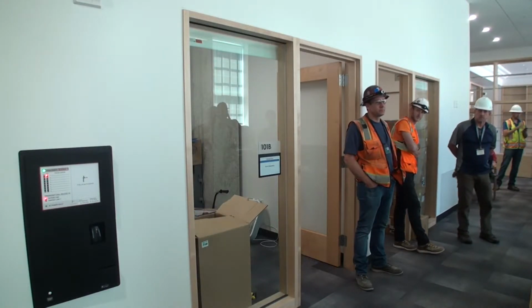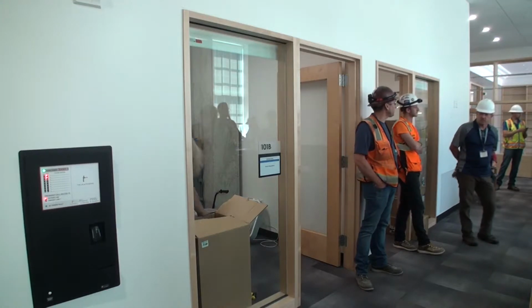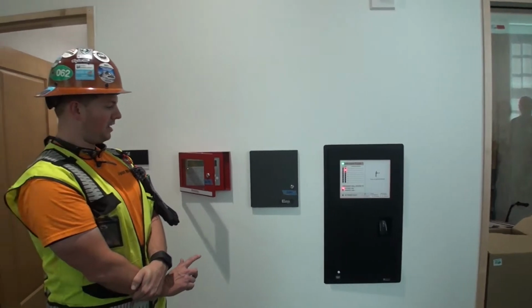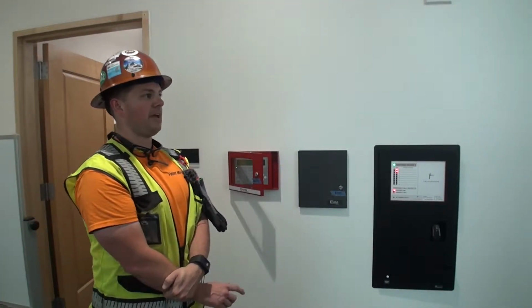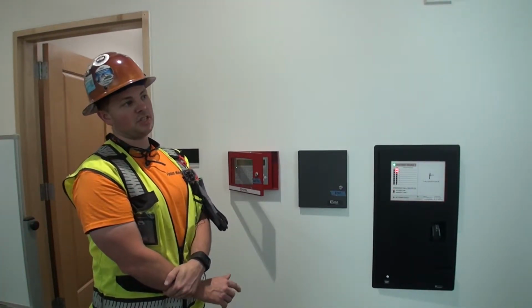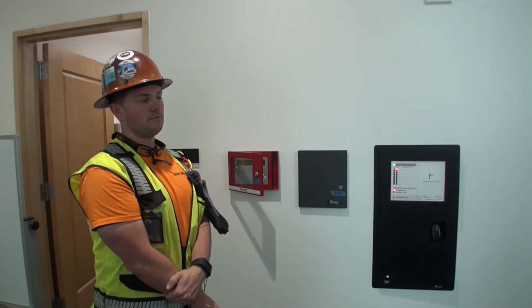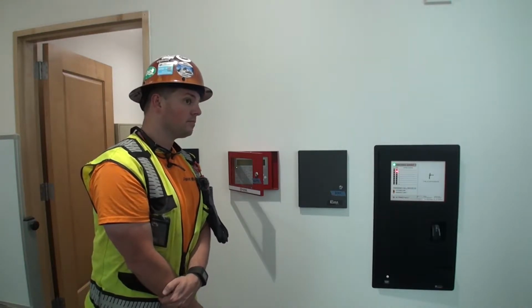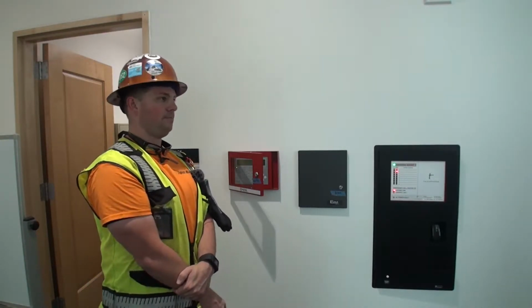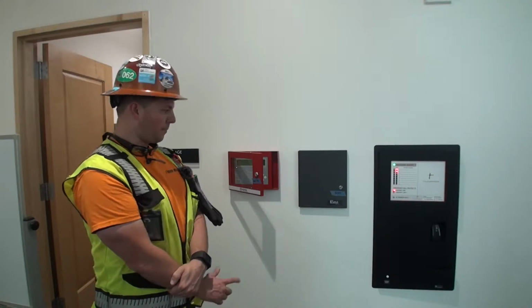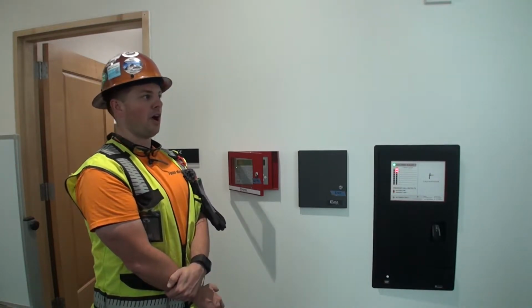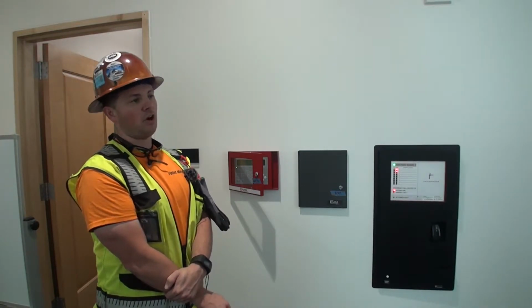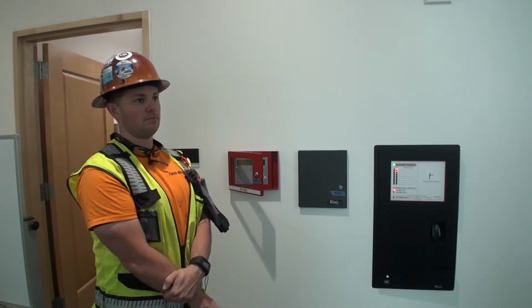Cool. Is this the only mic station, or is this one the main panel? This is the only remote microphone. The main voice evac panel has a microphone and switches to page specific zones. Which you can't override. What was that? You can't override down there. Yes, when you key the mic, it overrides. Up here, just pressing the microphone will override or start an all-call page. Down below, you probably have to activate all-call or a specific zone because you have the option between the two.